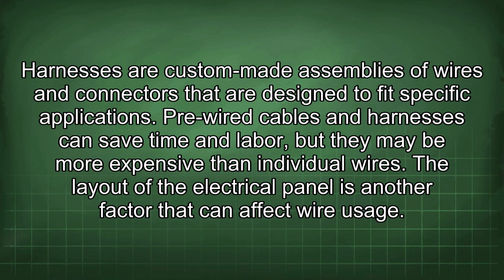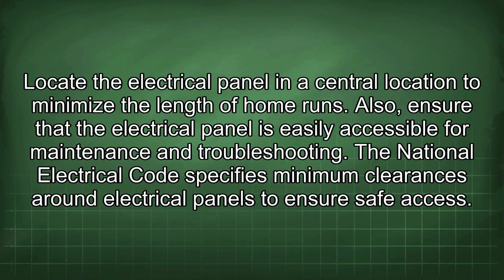The layout of the electrical panel is another factor that can affect wire usage. Locate the electrical panel in a central location to minimize the length of home runs. Also, ensure that the electrical panel is easily accessible for maintenance and troubleshooting. The National Electrical Code specifies minimum clearances around electrical panels to ensure safe access.